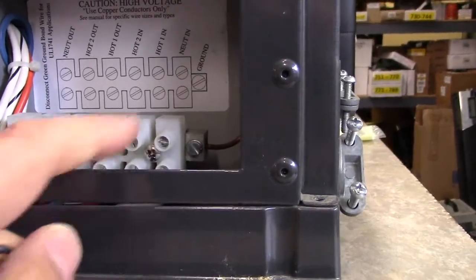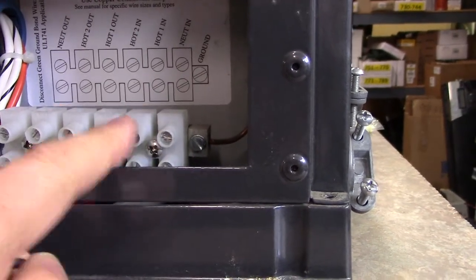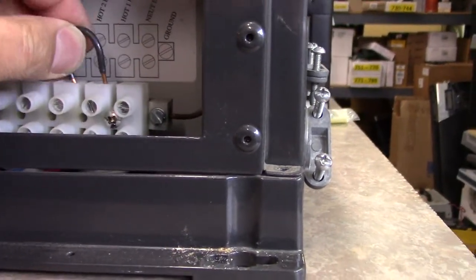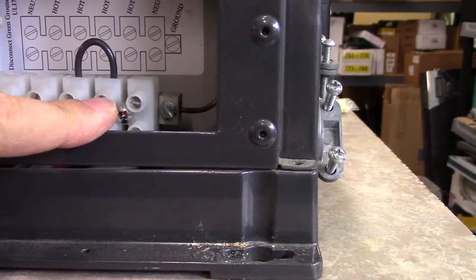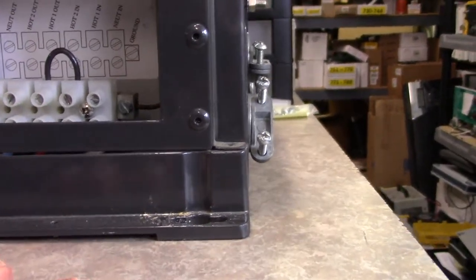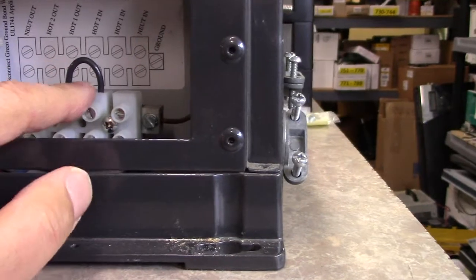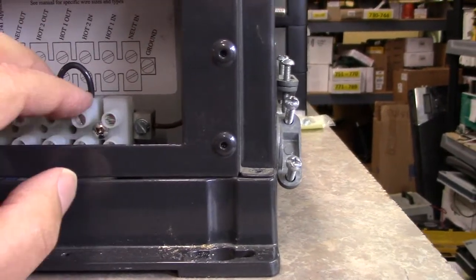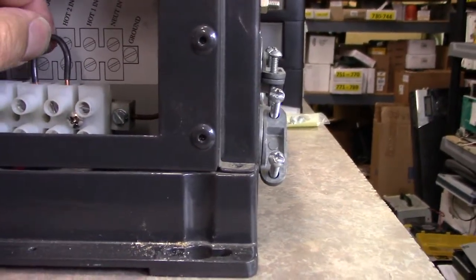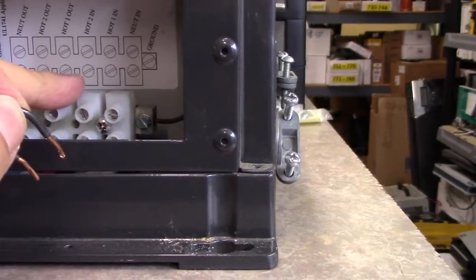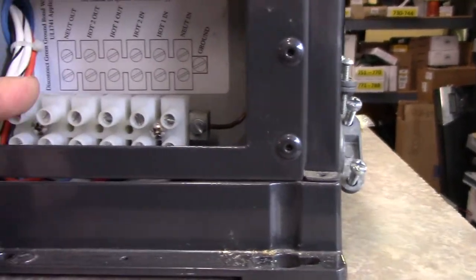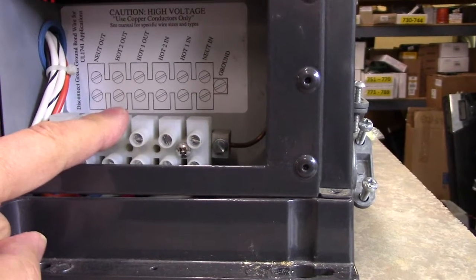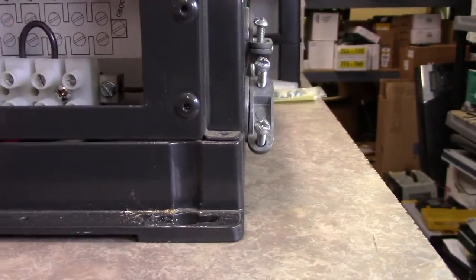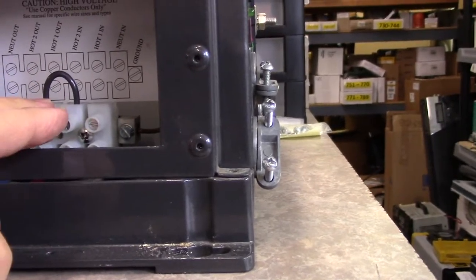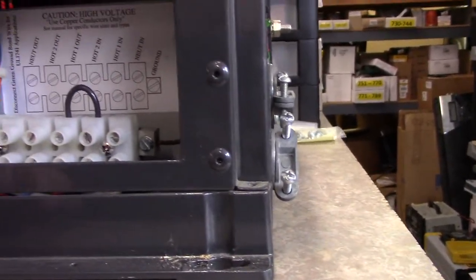Often you'll see the two inputs tied together, so you'll actually have a jumper in here like this tying the two inputs together. So if you only have a single AC wire coming in, sometimes you'll do this to give you input to both circuits through the inverter, and then you'll get AC coming out both outputs. If you don't need that, they often do it just to help increase the current capacity by having the two circuits going through the unit instead of just one.